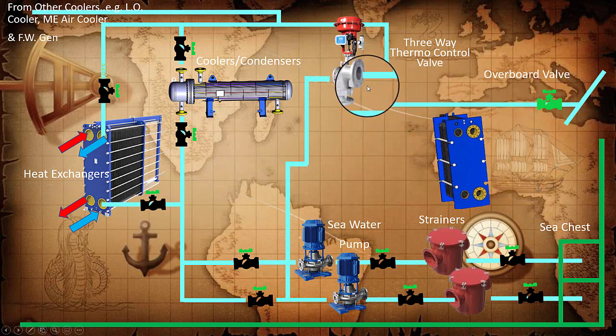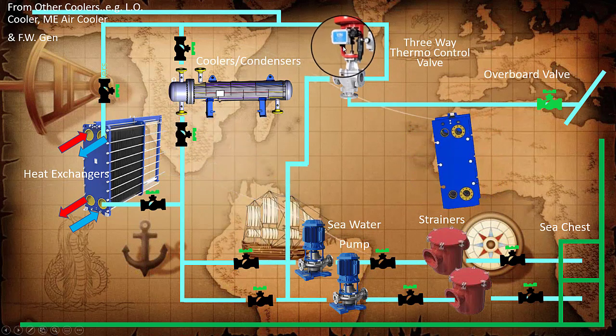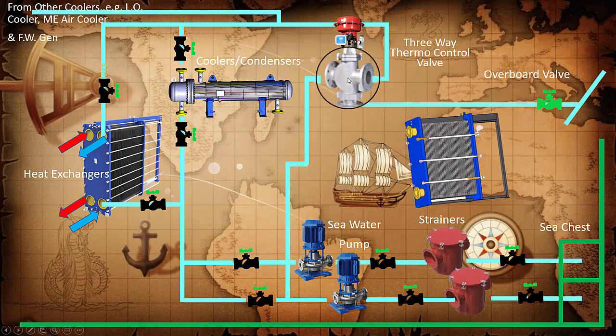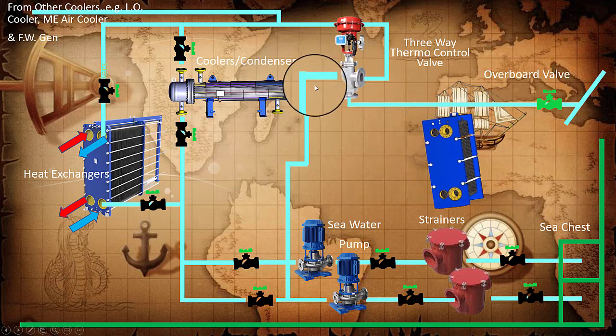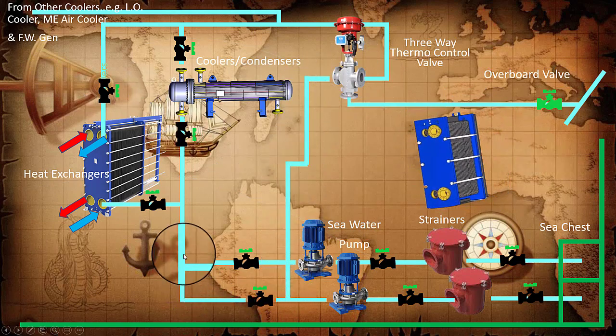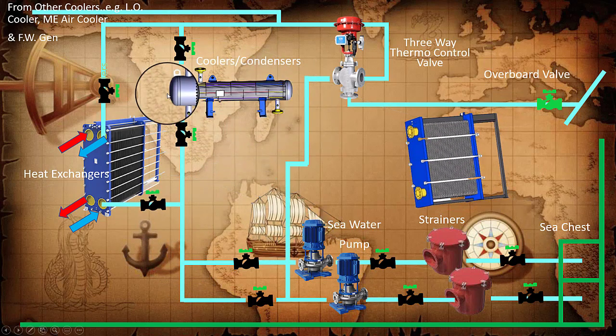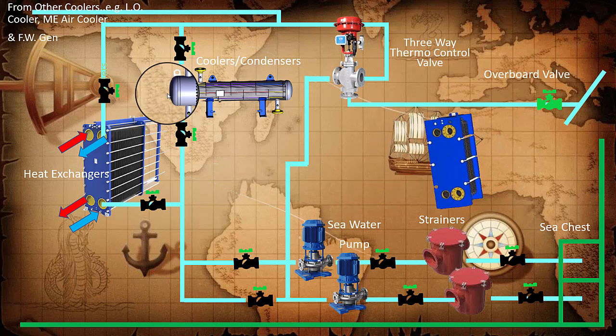As you can see through the lines, it supplies to the heat exchangers or coolers or condensers. It goes out and goes to the open cycle or overboard valve. If the temperatures have been met through the settings of the three-way thermocontrol valve, or mixing valve, it can also recirculate back. It will pump in and it loops in. This is the explanation of seawater cooling.